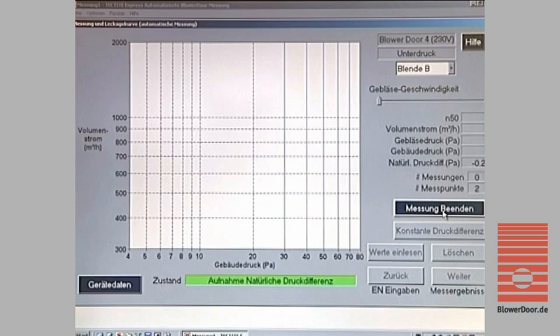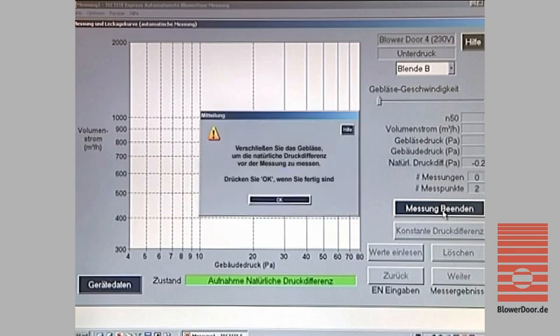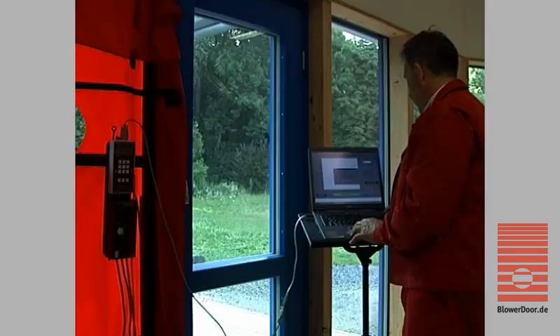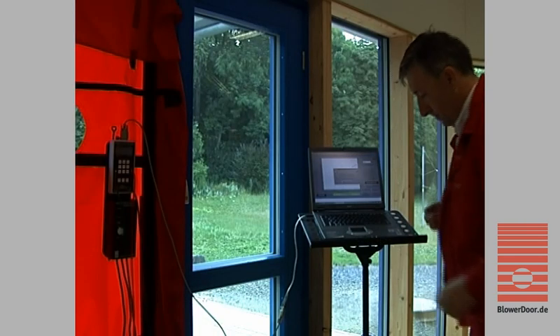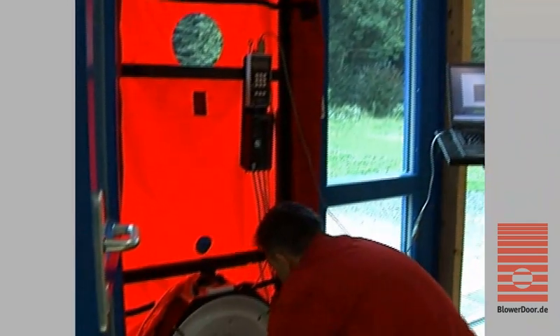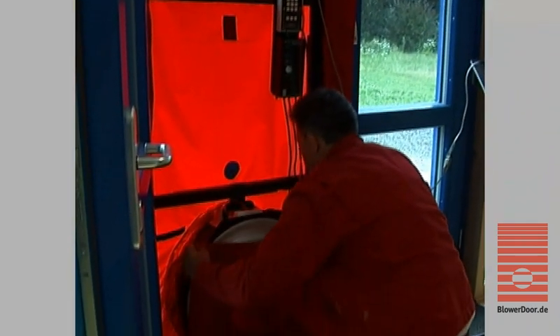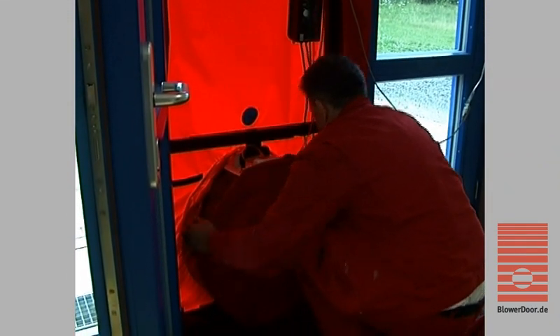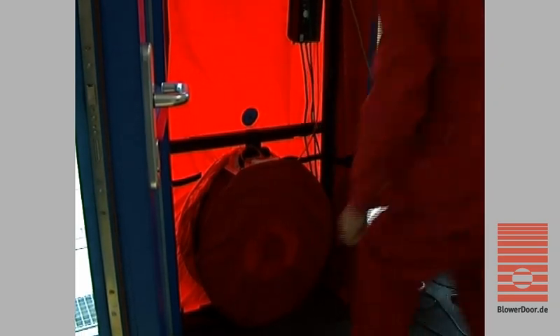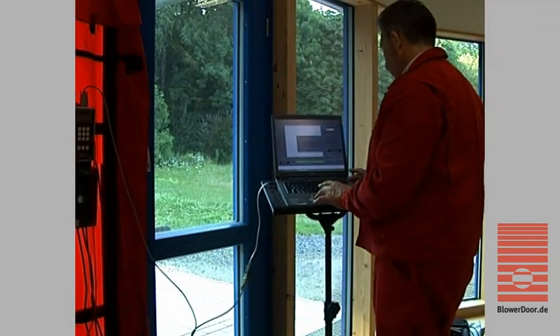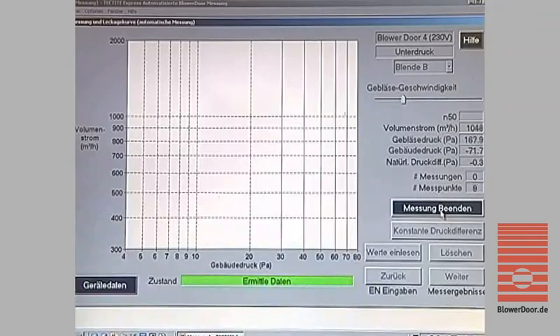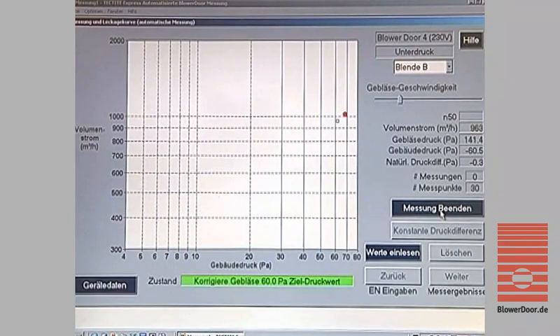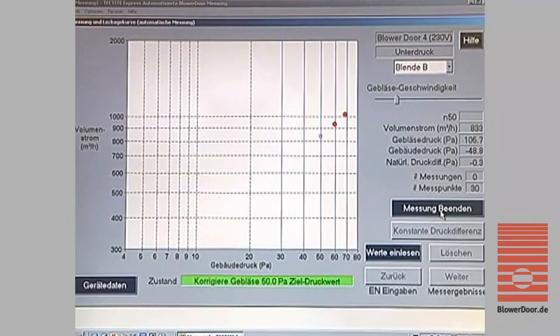The program provides easy-to-understand on-screen instructions, which eliminates operator errors and ensures consistency from test to test. To determine the baseline building pressure difference, the fan is covered with a nylon cap. After 30 seconds, the recorded baseline pressure values appear on the screen and the fan cap can be removed.